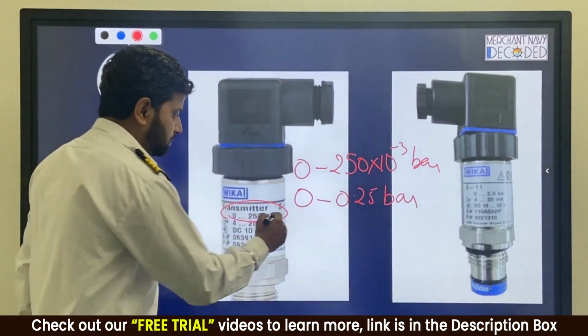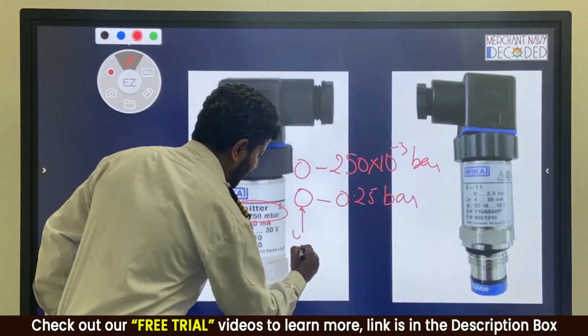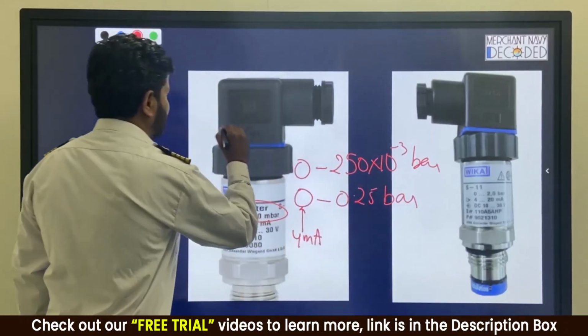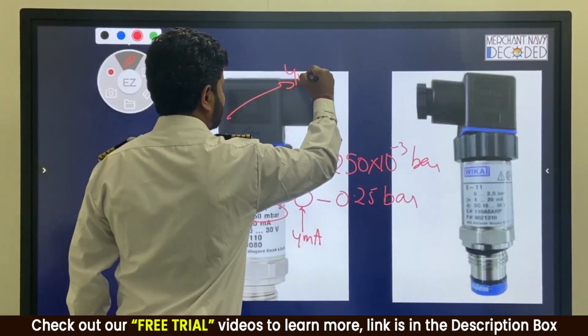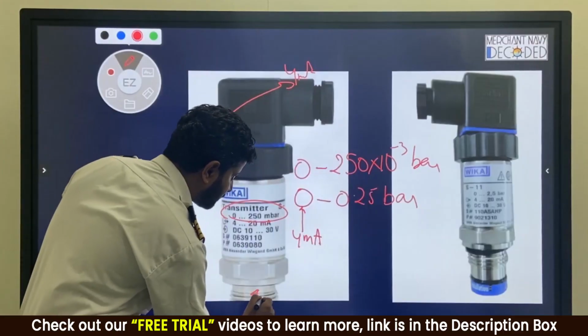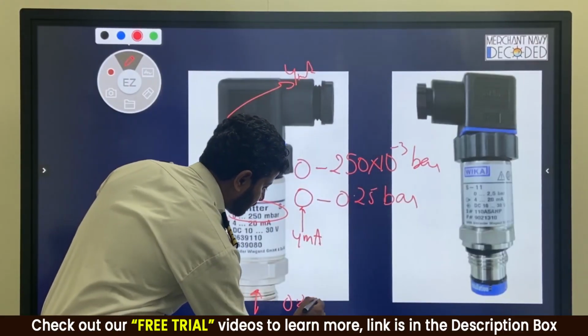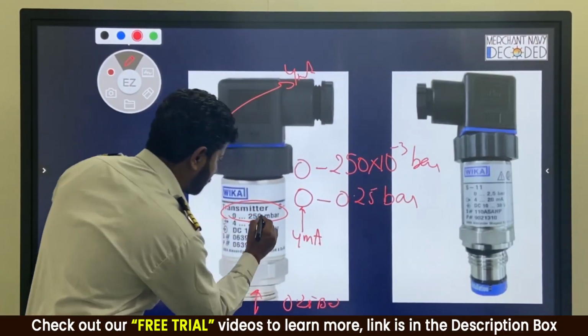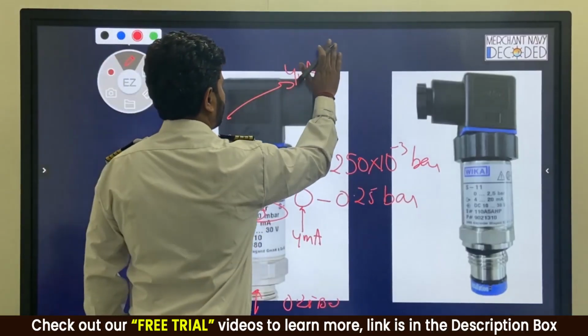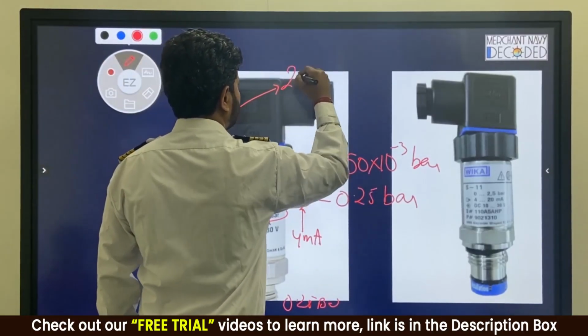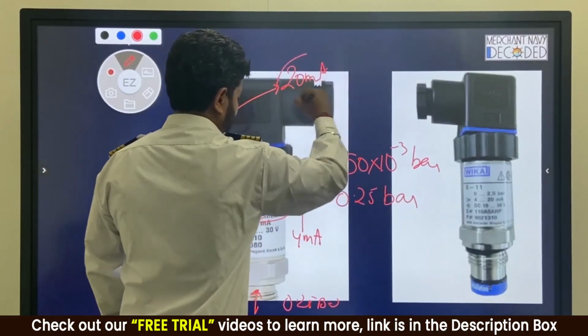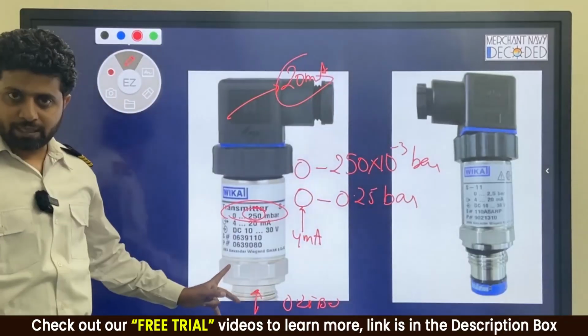4 to 20 milliamps. That means when 0 bar, the current coming from over here will be 4 milliamps. And when this pressure is reading 0.25 bar, 0.25 bar maximum, then the output current will be 20 milliamps over here. Copied, guys? समझ में आया?